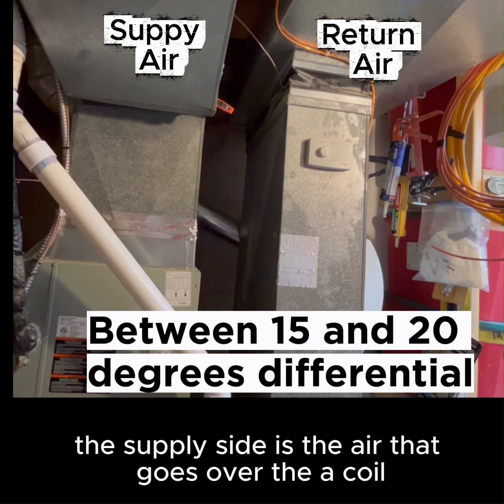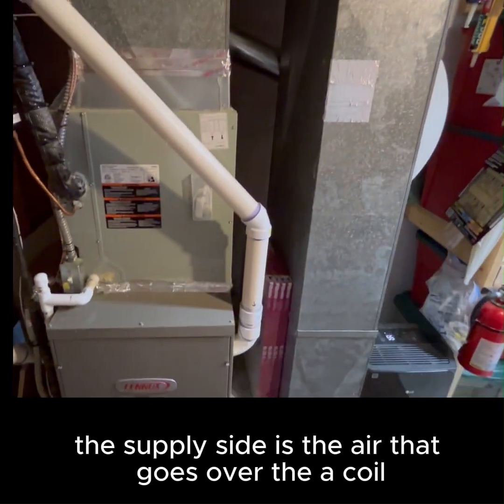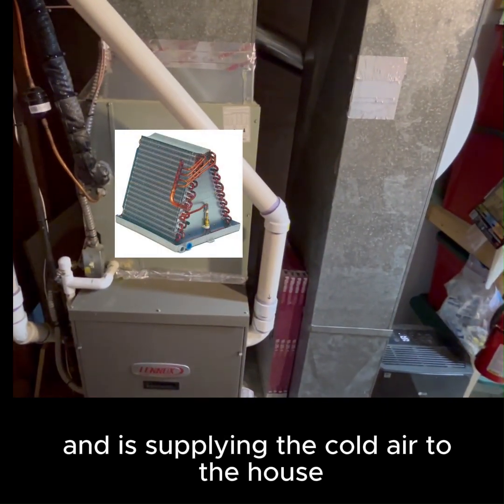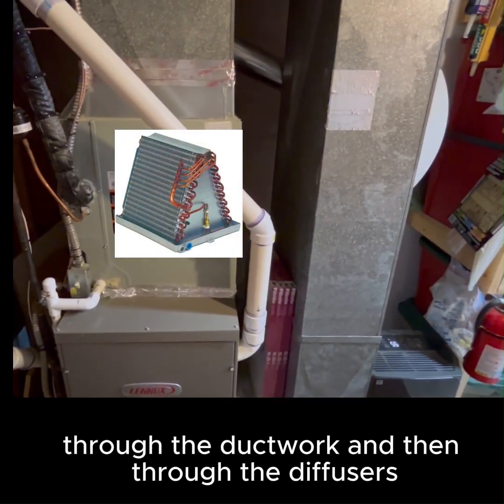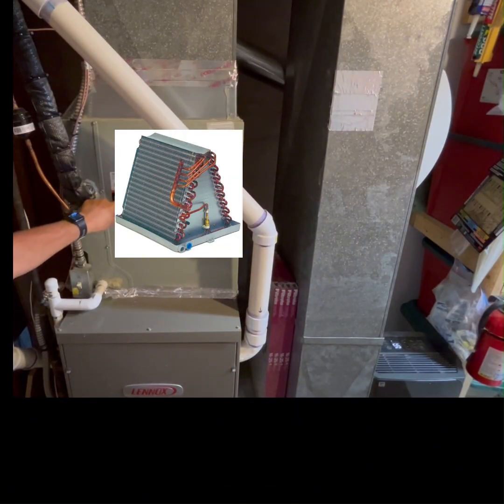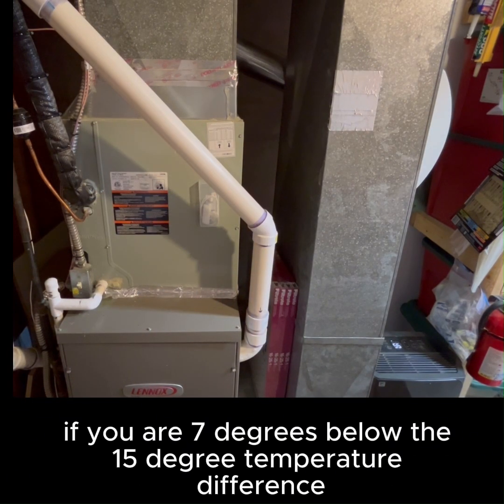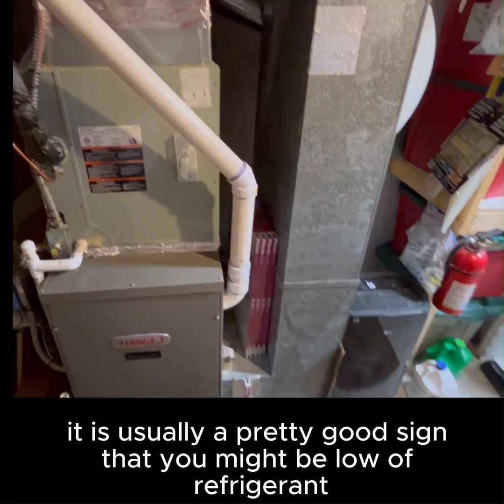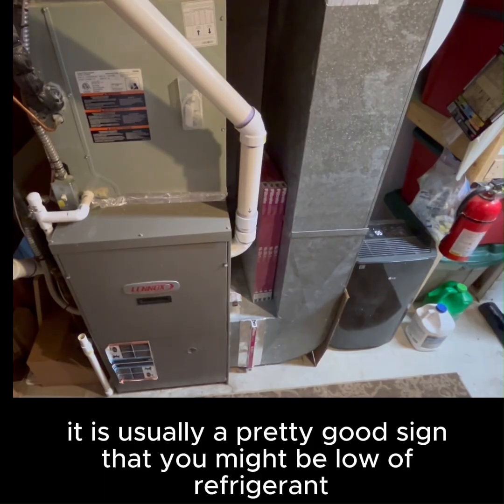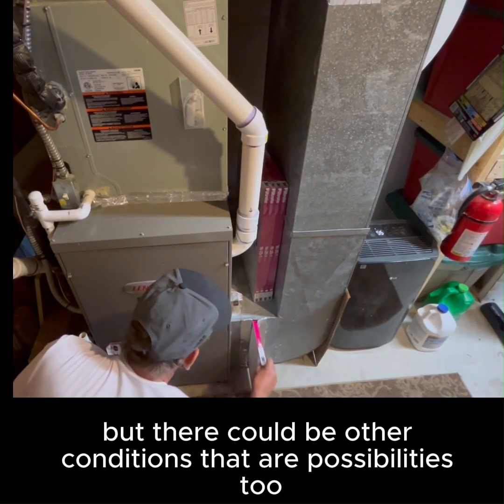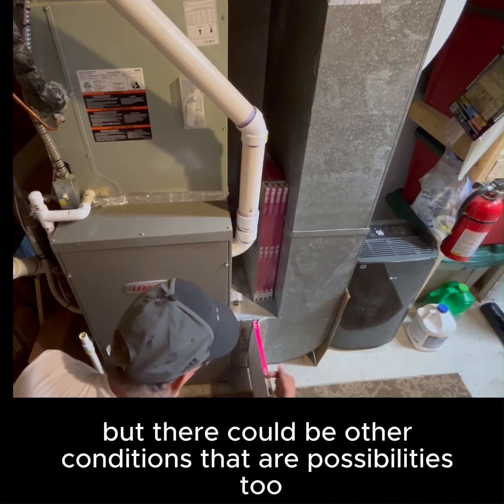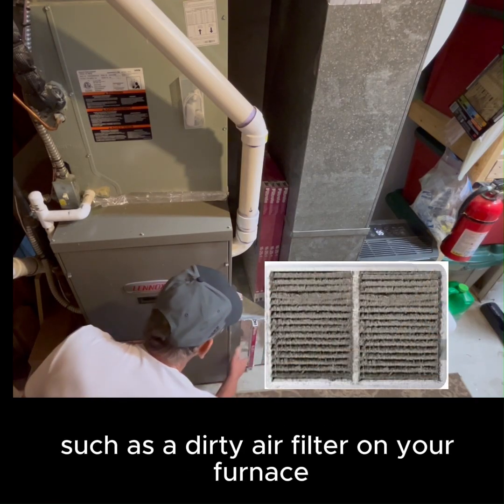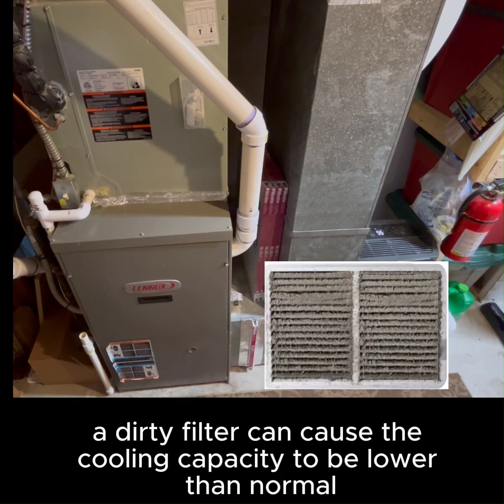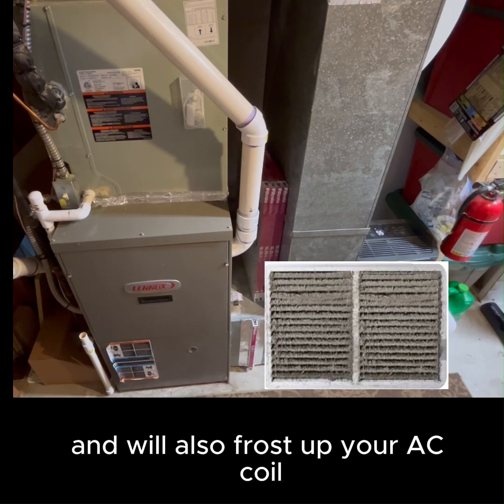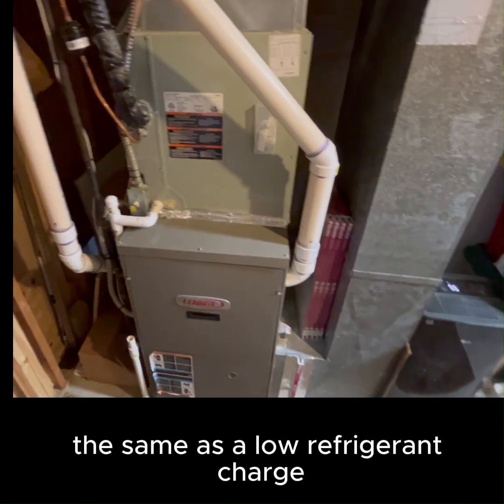The supply side is the air that goes over the A coil, which is the cooling coil, and is supplying the cold air to the house through the ductwork and then through the diffusers. If you are 7 degrees below the 15 degree temperature difference, it is usually a pretty good sign that you might be low on refrigerant. But there could be other possibilities too, such as a dirty air filter on your furnace. A dirty filter can cause the cooling capacity to be lower than normal and will also frost up your A coil the same as a low refrigerant charge.